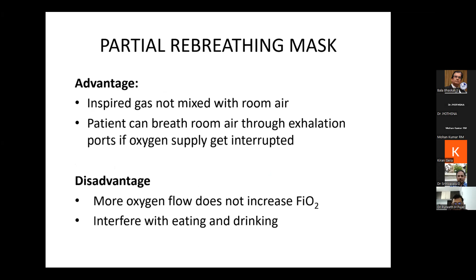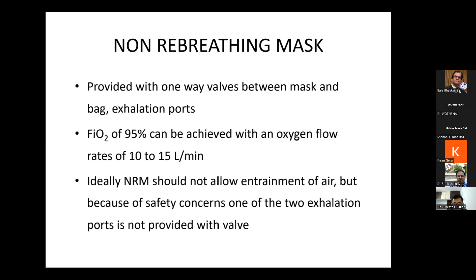Coming to non-rebreathing mask, here it is provided with the one-way valve between the mask and the bag and the exhalation ports. So this is the main difference from that of partial rebreathing mask. Here FiO2 of 95% can be achieved with oxygen flow rates of 10 to 15 liters per minute. Ideally, non-rebreathing mask should not allow entrainment of air, but because of safety concerns, one of the two exhalation ports is not provided with the valve.